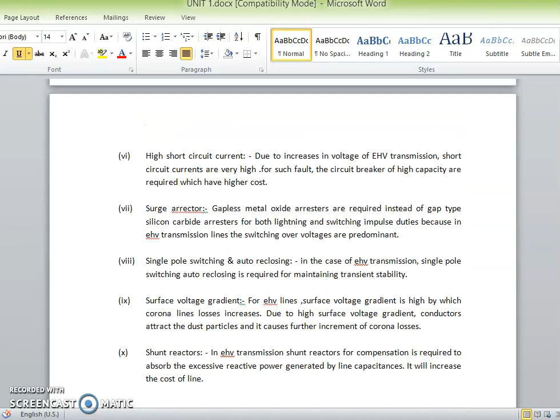High short circuit current. Due to the increase in voltage of EHV transmission, short circuit currents are very high. For such faults, circuit breakers of high capacity are required, which have higher cost. Surge arrestors, gapless metal oxide arrestors, are required instead of gap type silicon carbide arrestors for both lightning and switching impulse duties, because in EHV transmission lines the switching overvoltages are predominant.